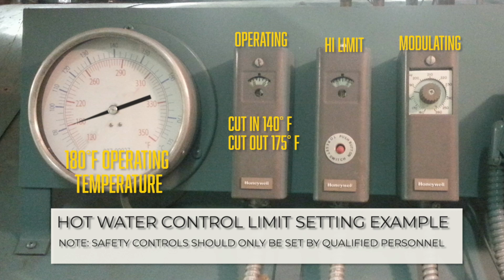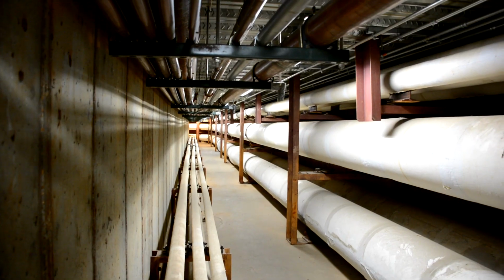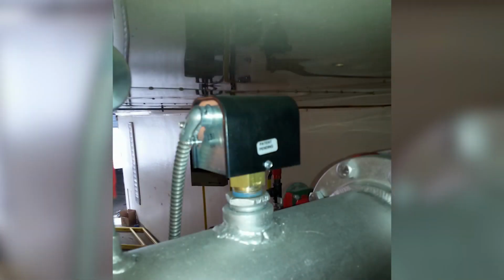And just like with the steam controls, there would be a high limit aquastat with a manual reset that would be set to ensure the temperature does not exceed that maximum desired set point. As mentioned, the hot water systems will need something to move this heated water from the boiler and into the system efficiently, and this is where circ pumps would be necessary. In order to effectively monitor the flow of the hot water, installed flow switches will verify the flow through the hydronic lines. These switches are simple designs with a paddle attached that will open or close a circuit when the flow is present.